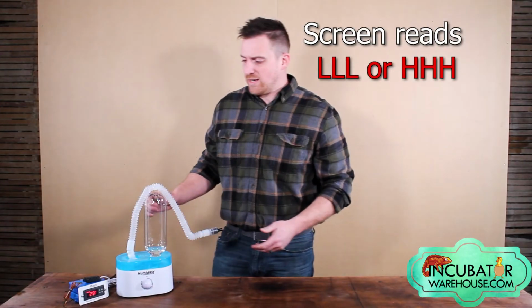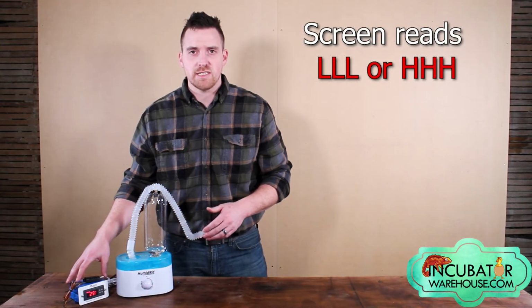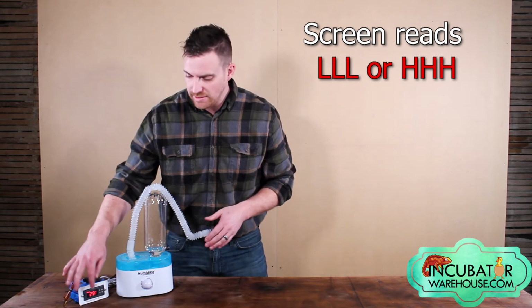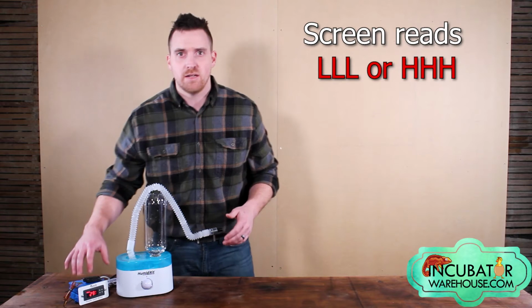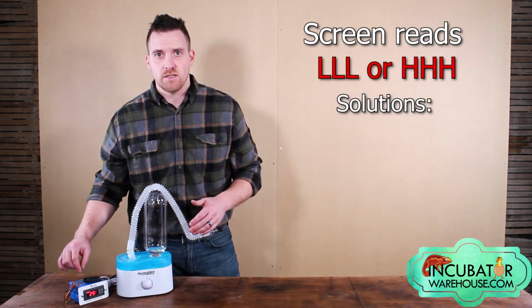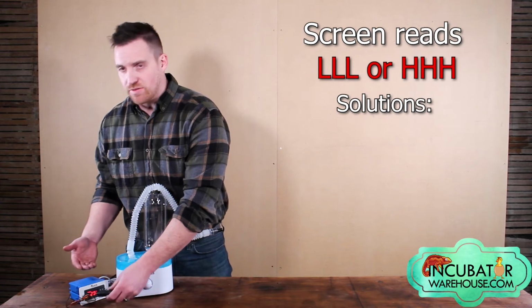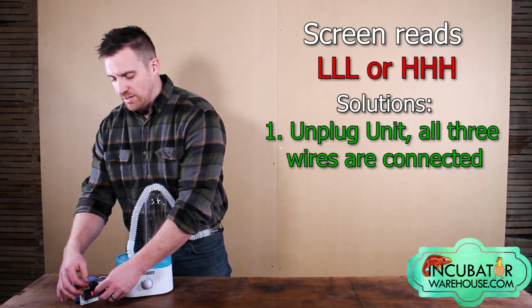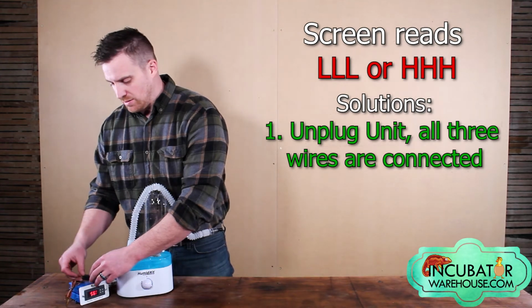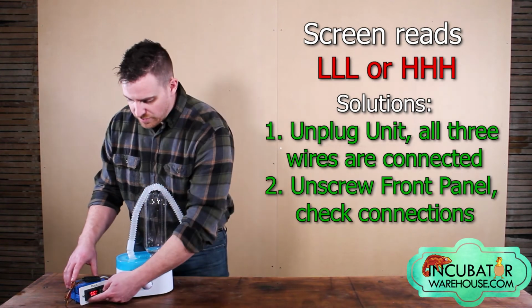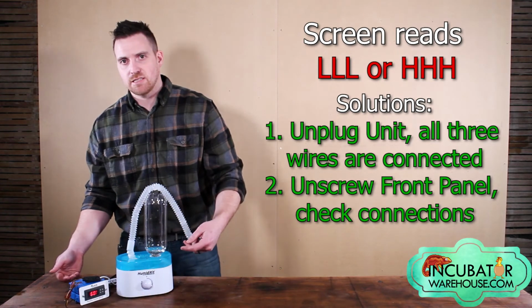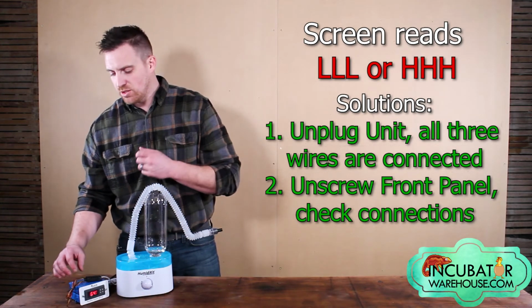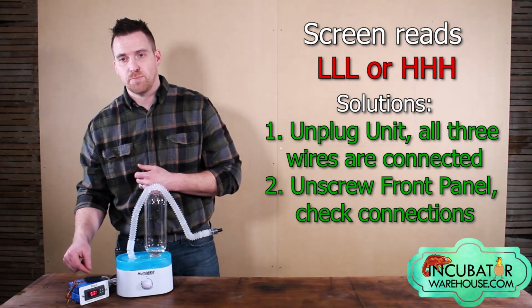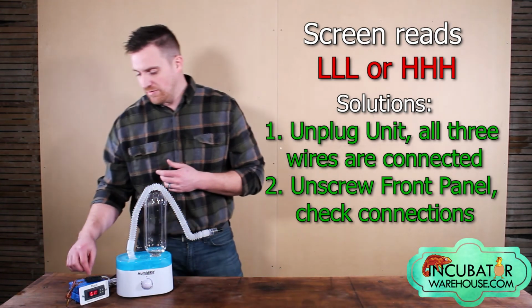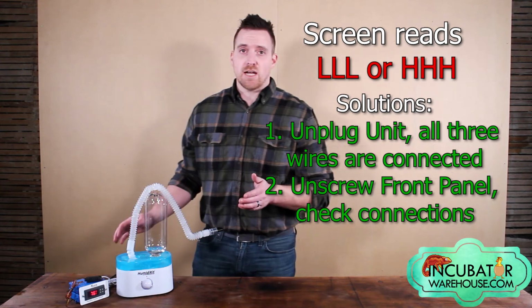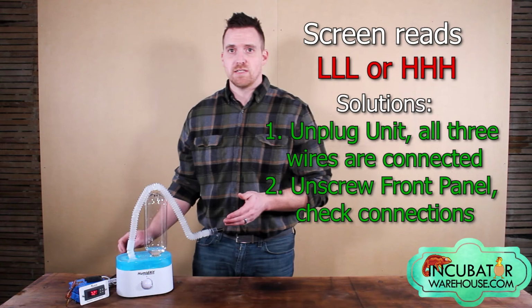One other issue you might encounter is if your control module screen reads LLL or HHH and does not show any of the percentages of the humidity. This typically is an issue to do with the sensor. Make sure to check both ends of the sensor after unplugging the unit and assuring it's turned off. All three wires should be connected, black, yellow, and red. You can also remove the two screws from the front and check the connections into the back. If everything looks to be securely fastened and the wires are in place in both ends of the sensor, you might have a defective sensor unit. At that point, please contact customer service and we can help get you a replacement sensor sent out as soon as possible.